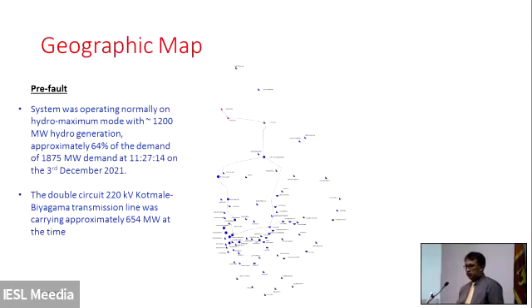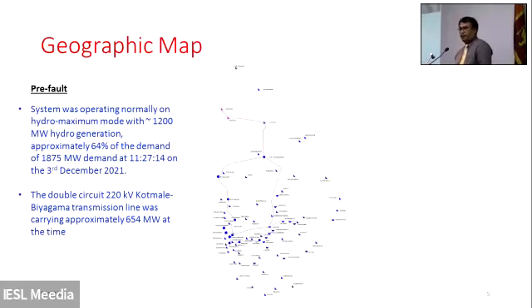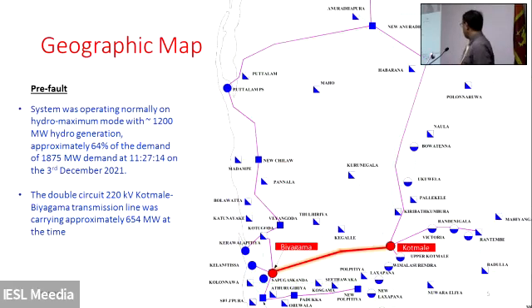Right. So let me take you through the incident that took place on the 3rd December. This is the Sri Lankan transmission network that you can see, and my focus is on this particular area because most of the things happened there. The pre-fault conditions: the system was operating normally in Hydromax mode, where the hydro generation was around 1,200 megawatts and the demand was 1,875. CEB colleagues can correct me later if the numbers are slightly different. This was the case at 11:27 and 14 seconds on the 3rd December. And the double circuit 220 kV Kothmale-Biyagama transmission line was carrying approximately 650 megawatts, which is shown in this diagram here.